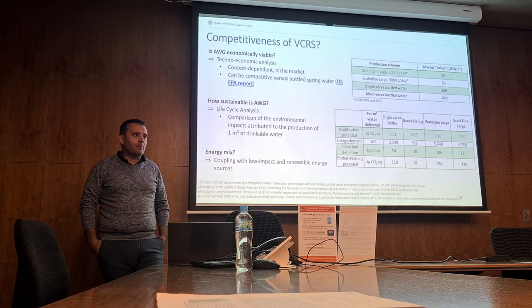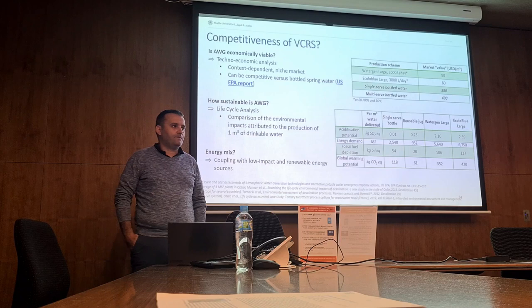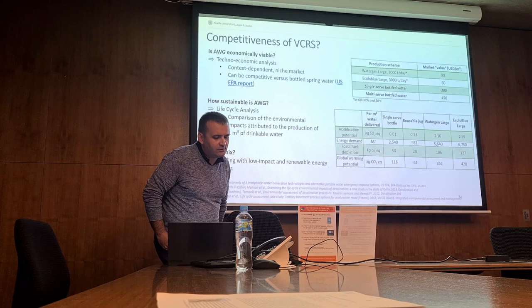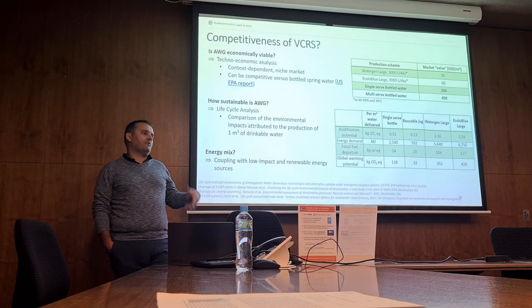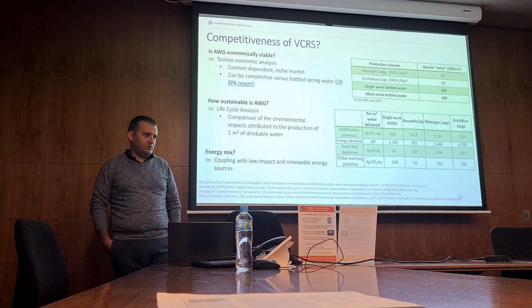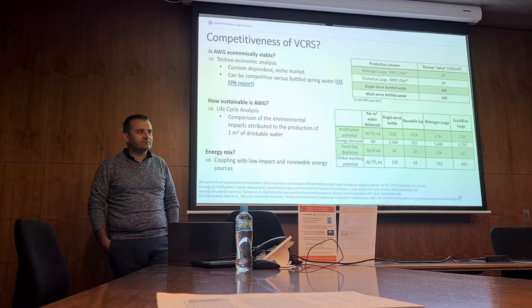So when you say failure, what exactly do you mean? You said between day and night. Well, we have up to 30 or 40 degrees variation of temperature between day and night in the desert sometimes. So that leads to some aging of some components. We have failures arising from freezing of some systems at night and then thawing in the morning, for instance, which has happened on different pumps and compressors. So this happens a lot. Okay, fair enough. Thank you for that.